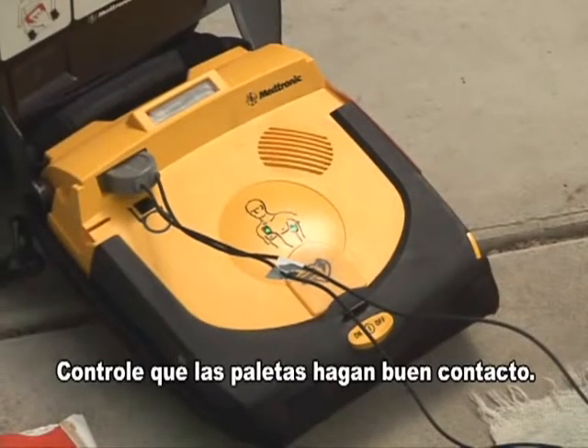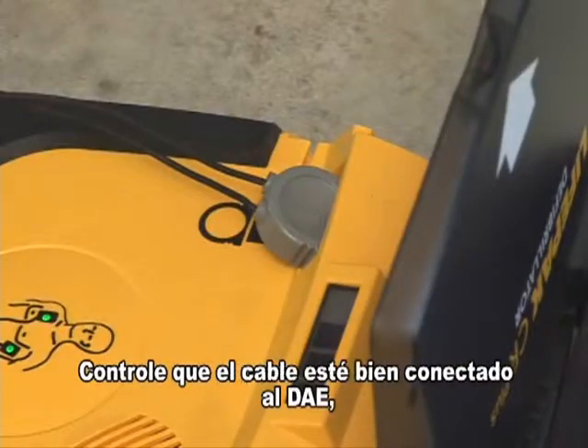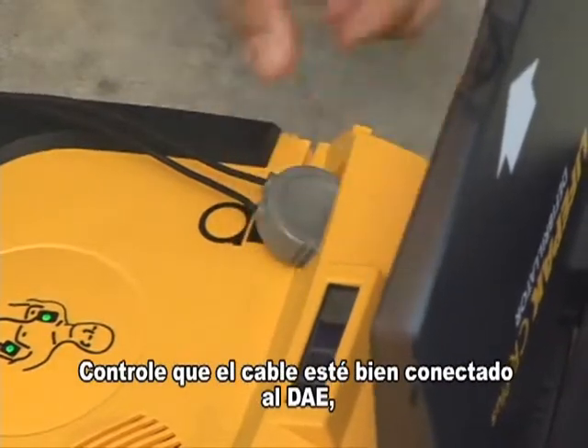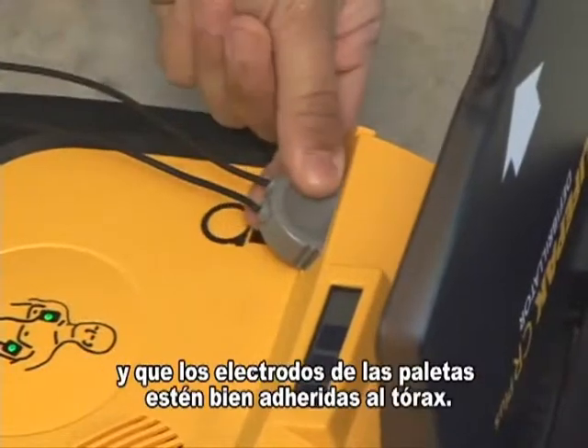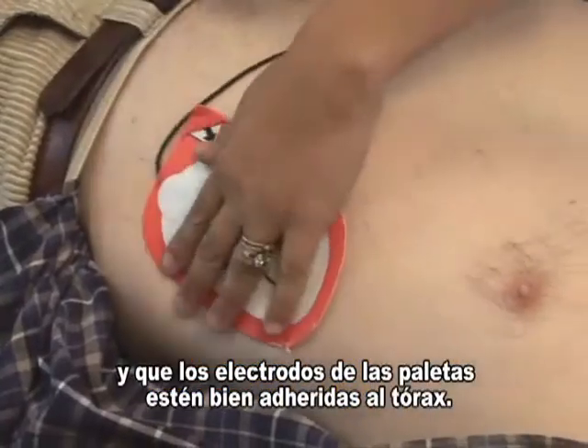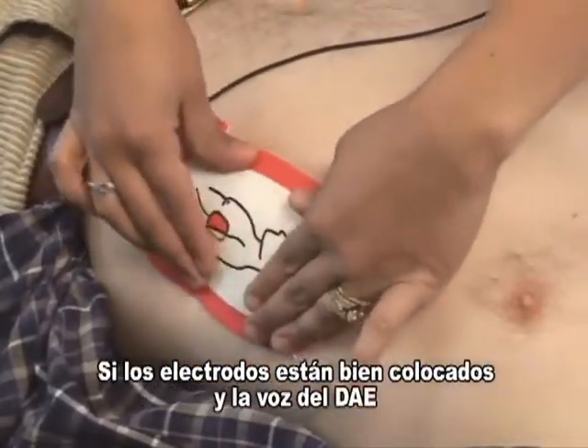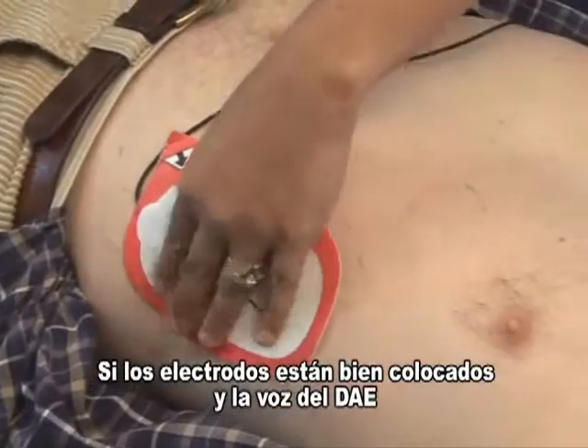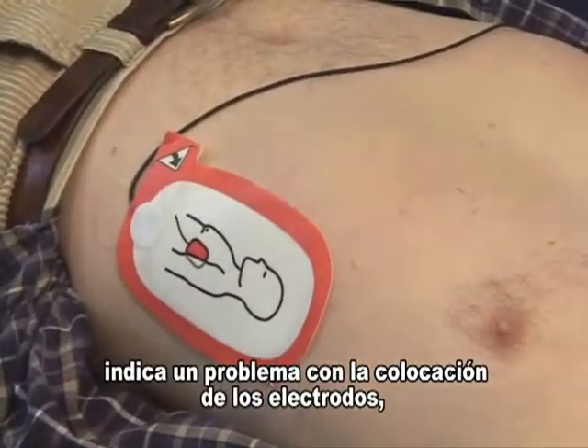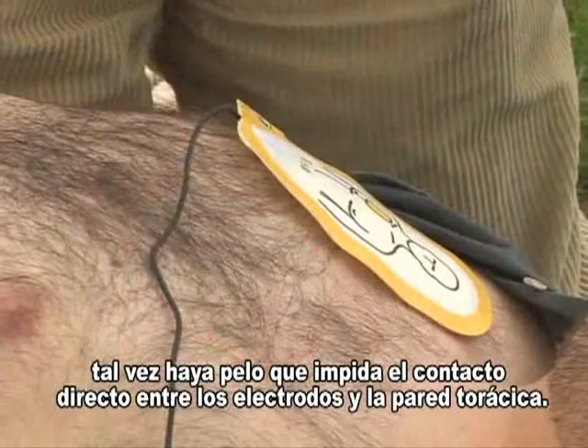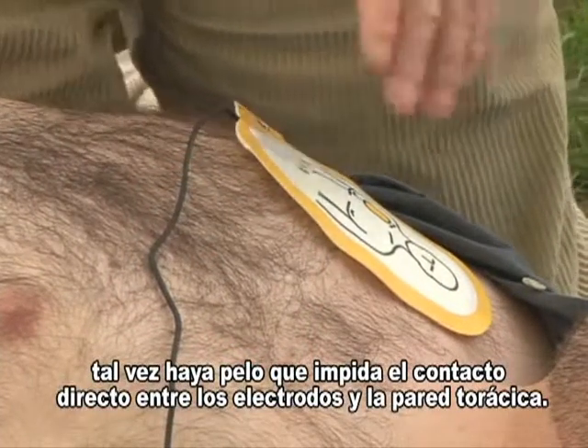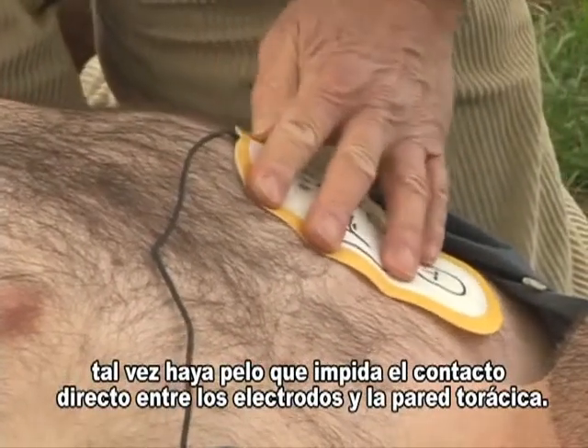"Check pads for good contact." Check that the cable is solidly attached to the AED and that the electrode pads are securely attached to the victim. If the electrodes are in place and the AED voice prompts indicate a problem with electrode placement, hair may be getting in the way of direct contact between the electrodes and chest wall. Use a razor to quickly shave the hair in the area of the pads.